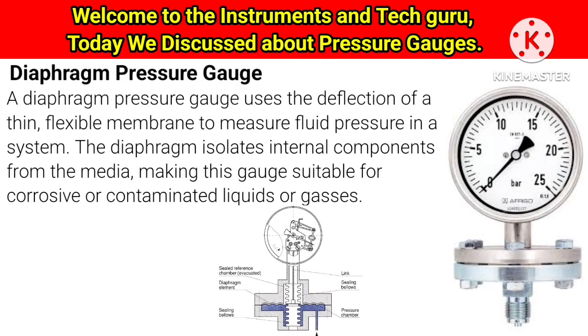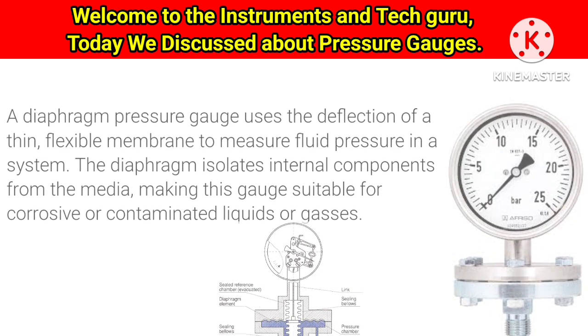indicate pressure. A diaphragm pressure gauge uses the deflection of a thin, flexible membrane to measure fluid pressure in a system. The diaphragm isolates internal components from the media, making this gauge suitable for corrosive or contaminated liquids or gases.